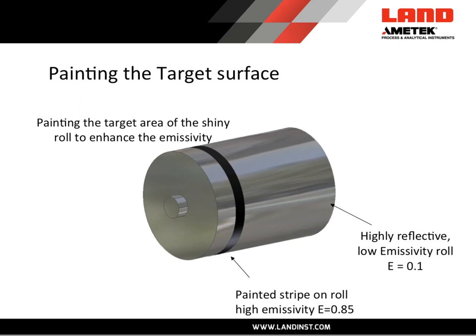Sometimes if you have a problematic, very low emissivity material, it's possible to raise the emissivity by doing something to it. In this example we see a chrome plated roll typical to what would be used in a paper mill. The surface of that chrome plated roll is very reflective with a very low emissivity value of 0.1. However, if you pick a part of that roll towards the edge and not in contact with the paper, you may be allowed to paint a stripe on that roll and measure the temperature of that stripe, because that paint would have a much higher emissivity of 0.85 and be very easy to measure.